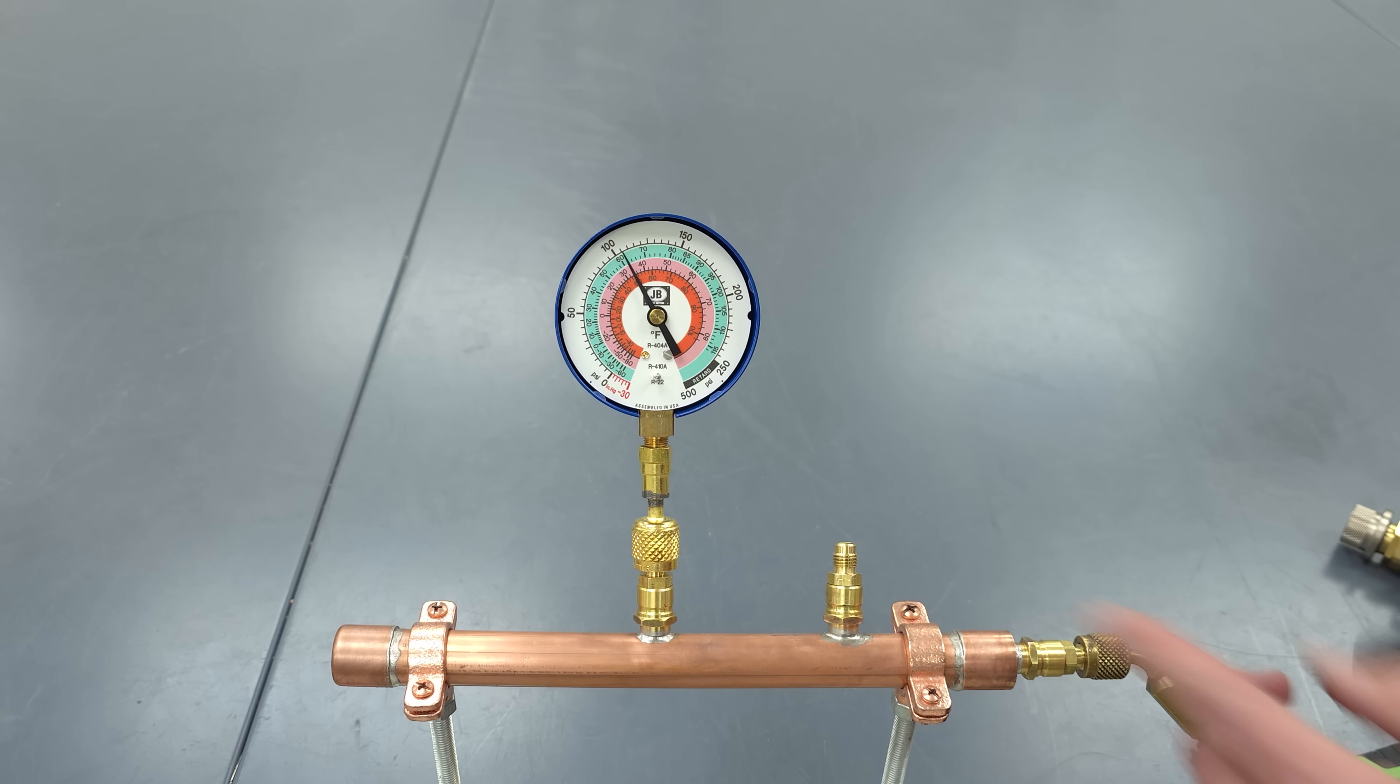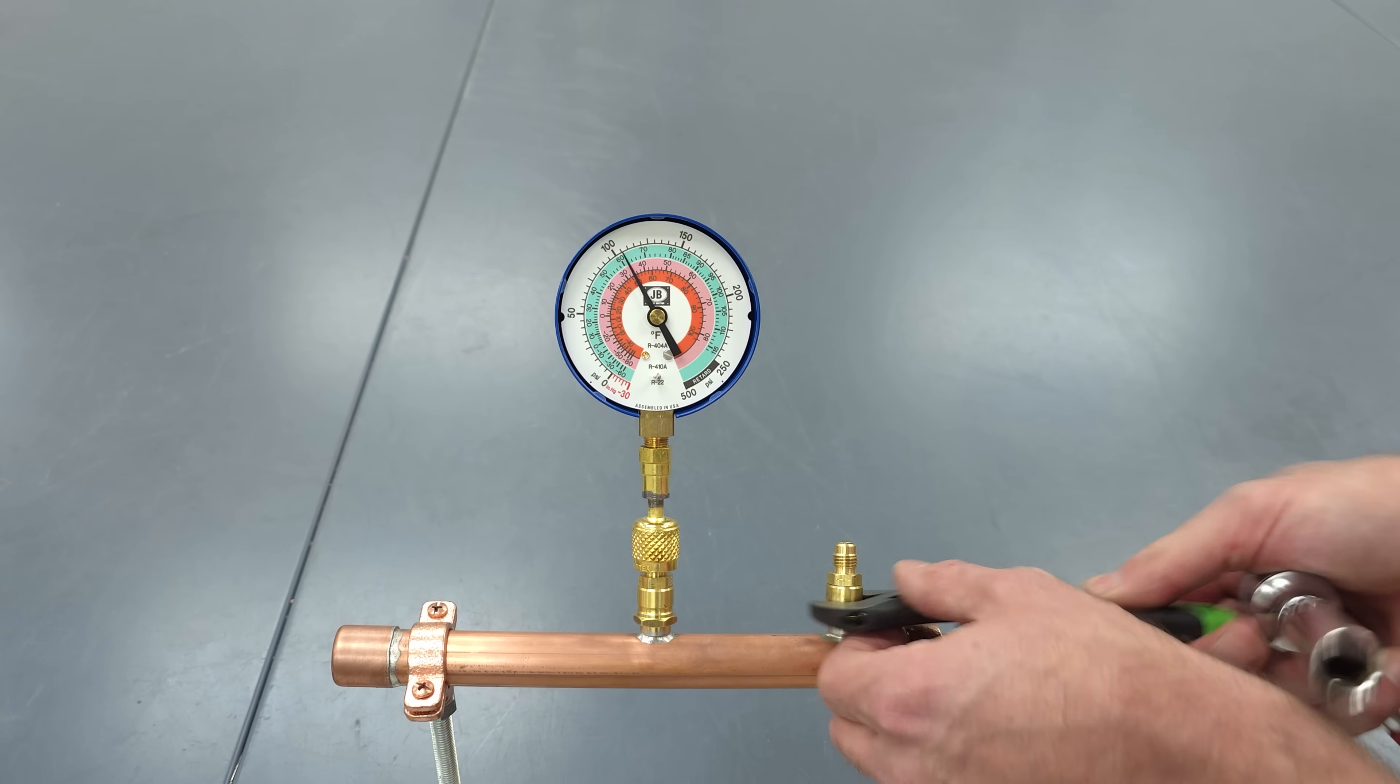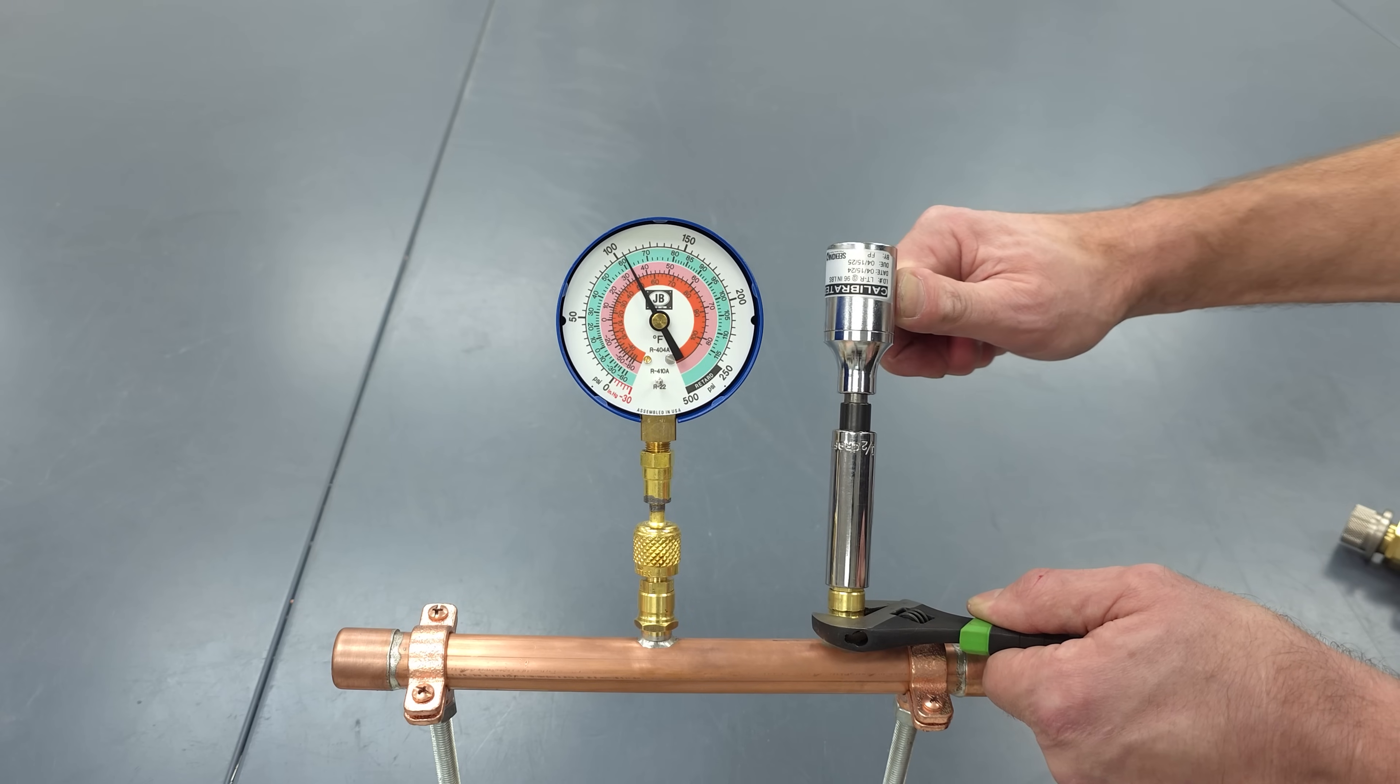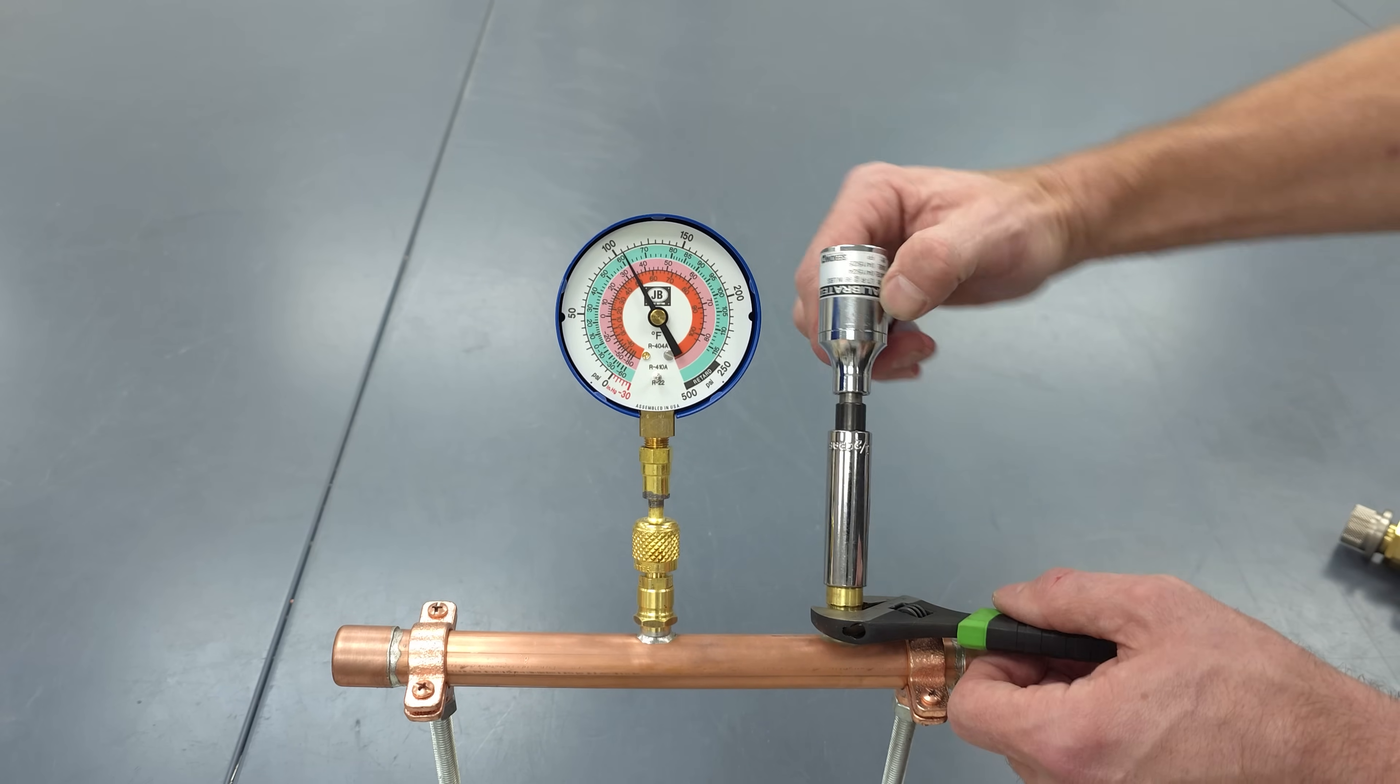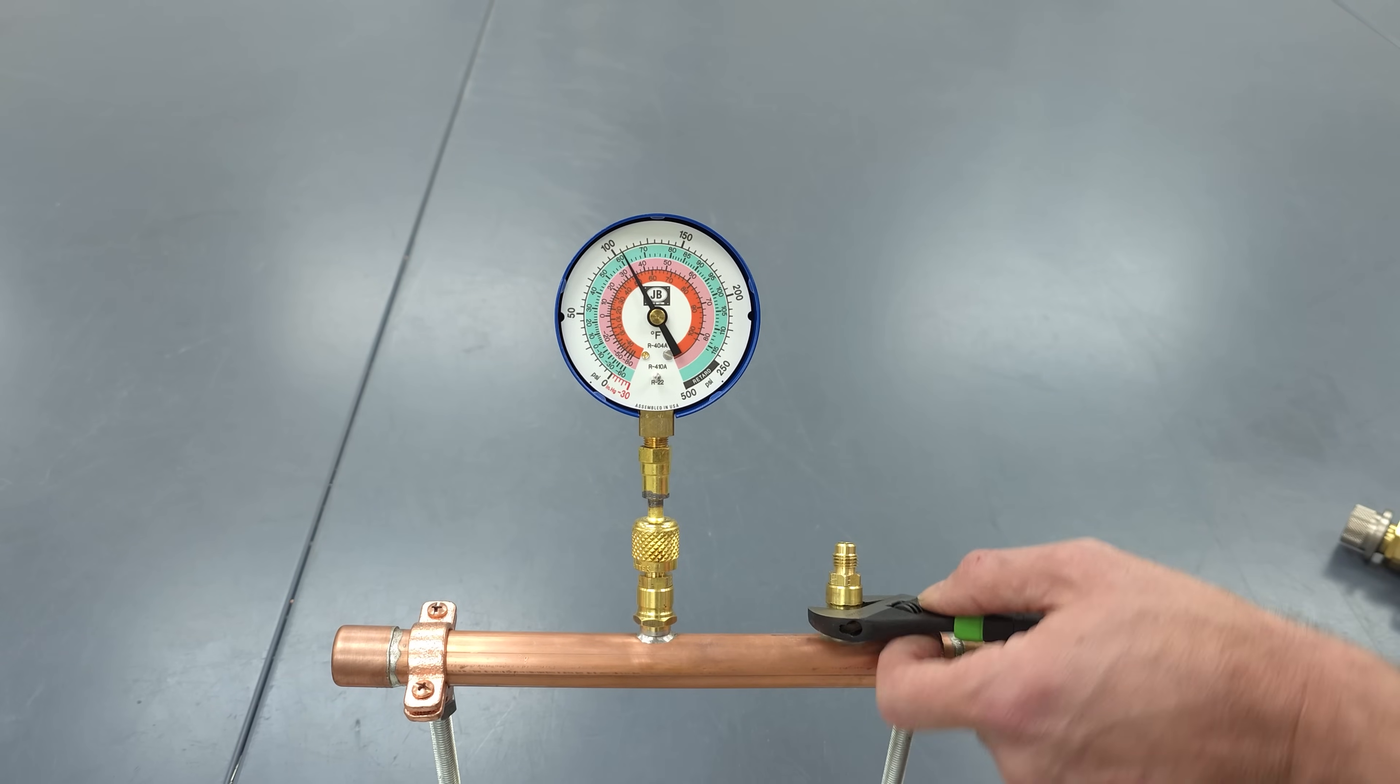So we're good now you can use a torque wrench in order to tighten this down it's 96 inch pounds. If you're going to do that you want to make sure that you're holding this with an adjustable wrench. And so this one specifically made to be torqued with this tool right here. And so as soon as I feel it kind of catching I know that we are fully torqued down.